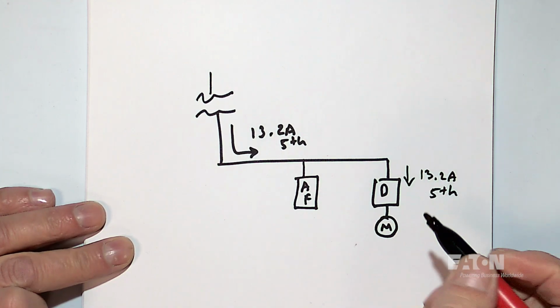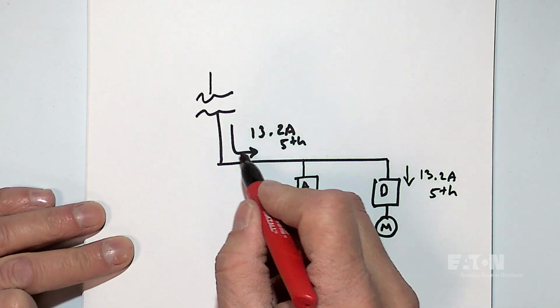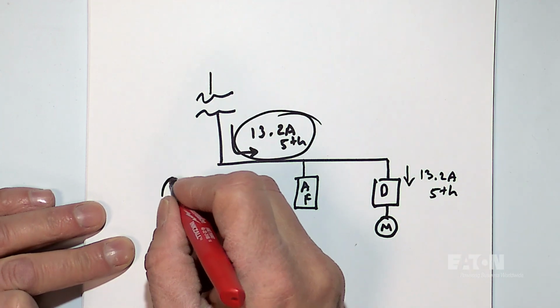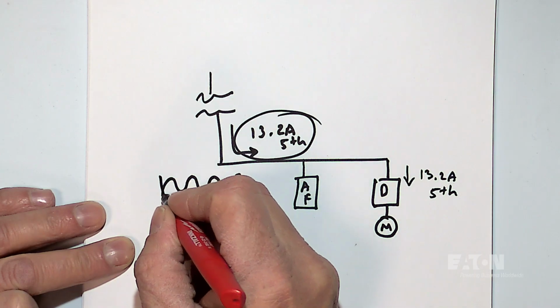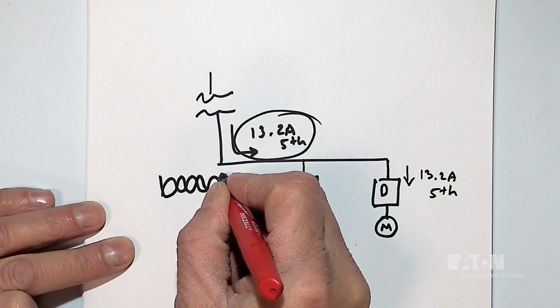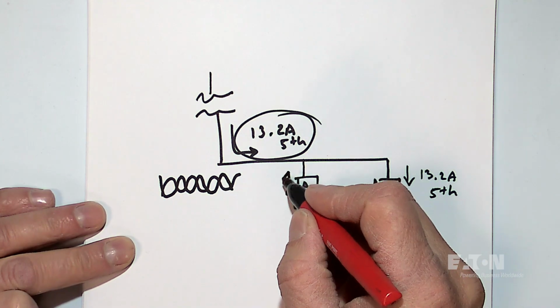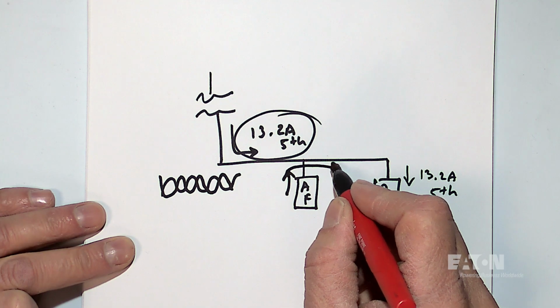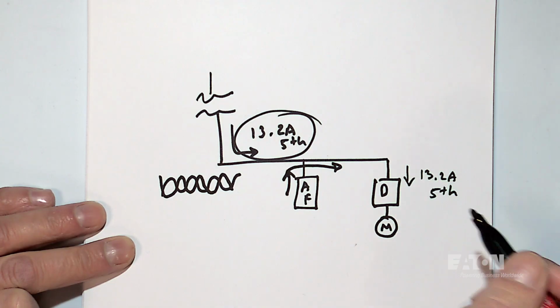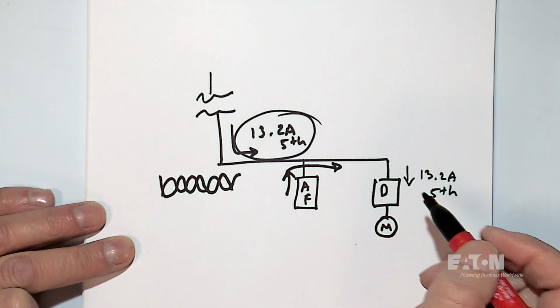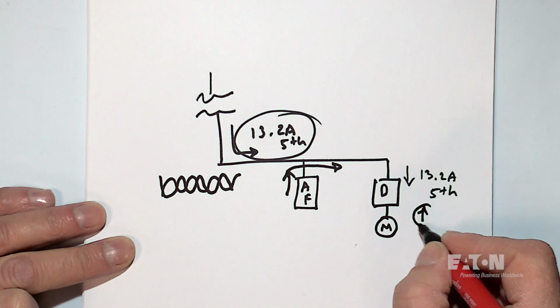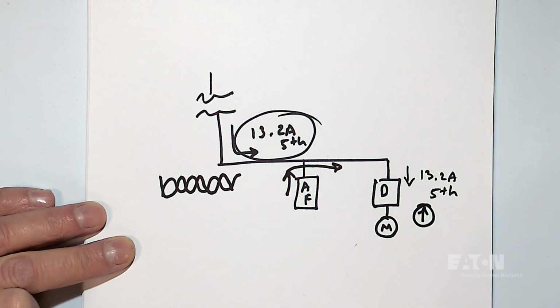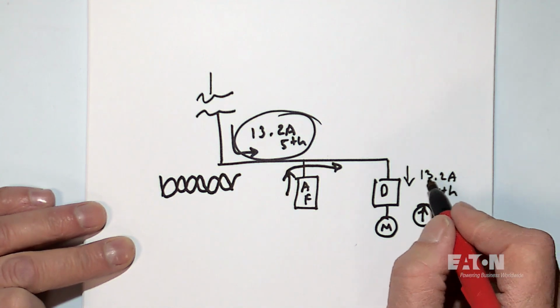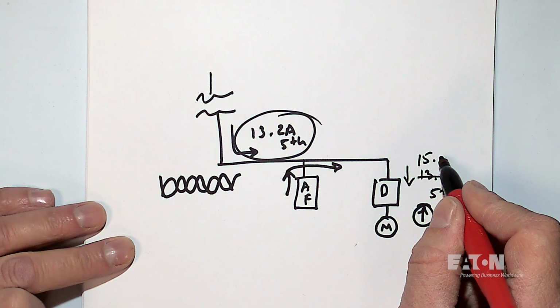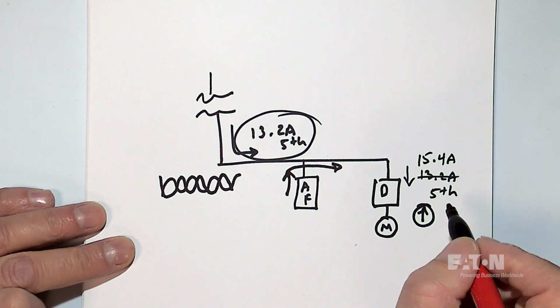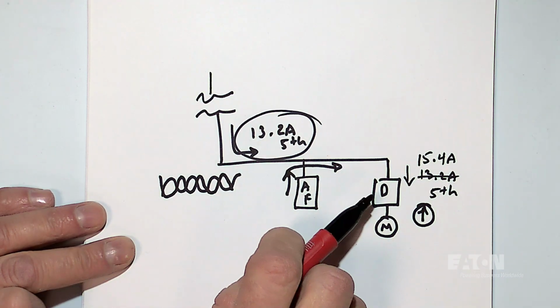And then the next thing we did was we put on the active filter, and this kind of went away because, of course, what we're doing is injecting equal and opposite currents. So this actually injects current toward the load, and by doing that, it negates what's going back to the source. Because remember, the harmonic current comes from the load and flows back out onto the system. So why does the harmonic current increase to 15 point something here? I think it was like 15.4 amps. Why does it increase when I put that active filter on?